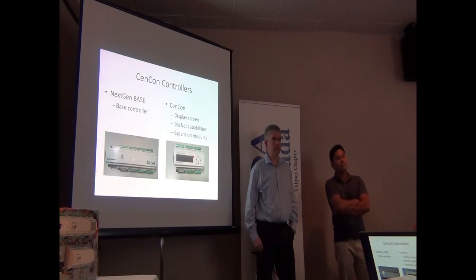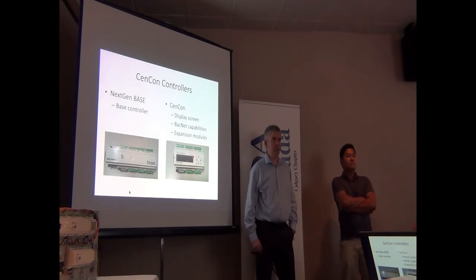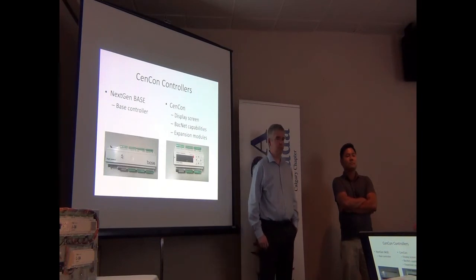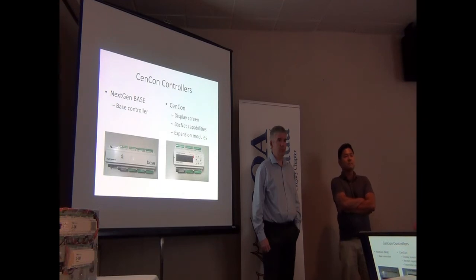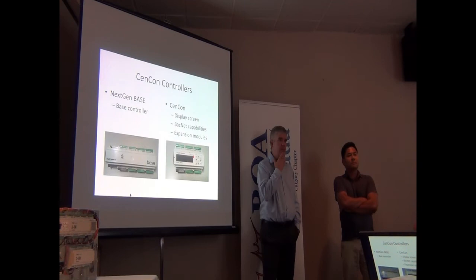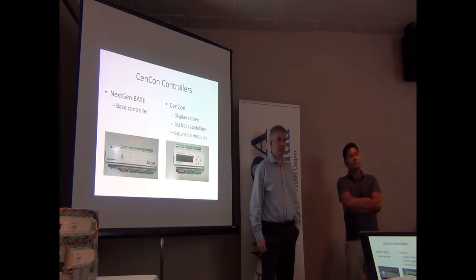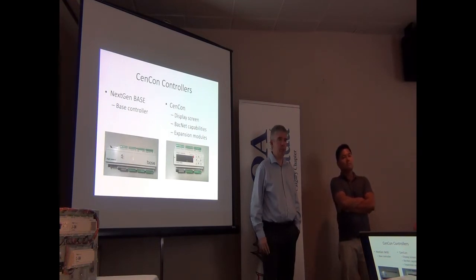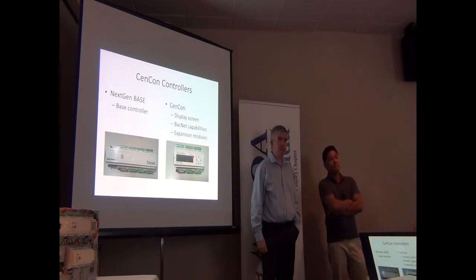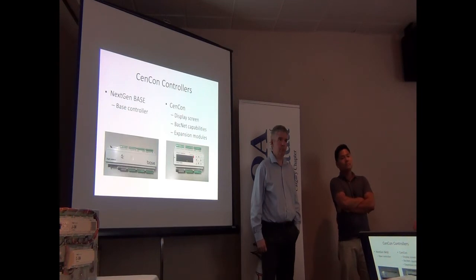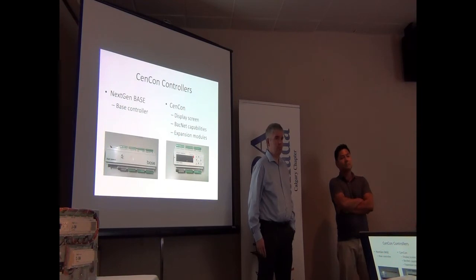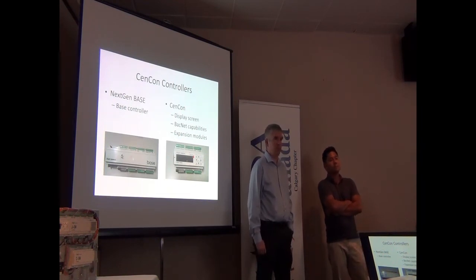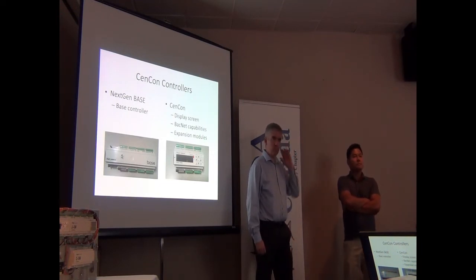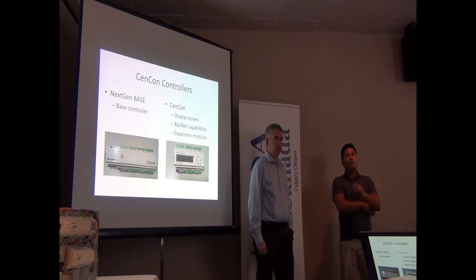So I'm wondering, are you able to update that software, because each unit is specially designed for its purpose? And we're adding cooling, so we talked about adding existing controllers so they control the additional cooling. My question is, is the proprietary software available, or do we have to rebuild a controller to match the addition of cooling? In my experience, proprietary programming in these controllers has posed a bit of a problem with adding more. Does engineered air allow us, or is able to sell us, the upgraded software or program for the controllers?